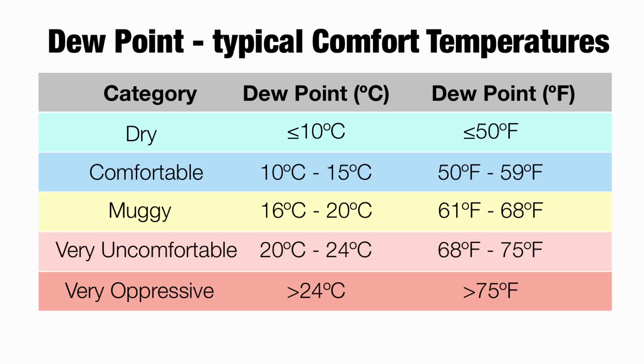So the dew point is a temperature at which we have complete saturation of the air with water, so 100% relative humidity. Right, yeah. And this kind of number is an interesting number because we do have ranges where it doesn't matter what the actual temperature is, if the dew point is at a set point, we can feel a certain level of comfort. So what I'm trying to say here is, if the dew point is between 10 degrees and 16 degrees, that is typically comfortable. Okay.